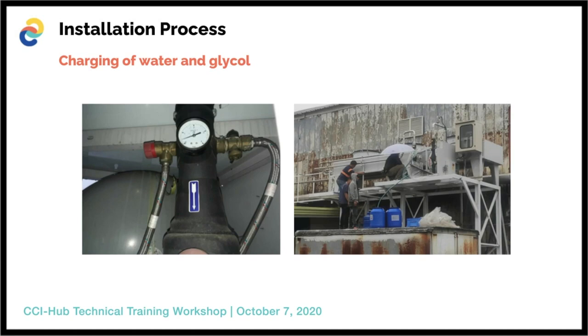This procedure uses a 50-50% ratio of mineral water and glycol in the systems. Water turns into steam at 212 degrees Fahrenheit. Mixing ethylene glycol antifreeze with water in a 50-50 ratio increases the boiling point to 223 degrees Fahrenheit. We're using a food-grade glycol with anti-corrosion effects on copper, stainless steel, and other metals. We use an external pump to charge in the mixture of mineral water and glycol in our system, and we also install air purging systems to remove air bubbles in the system.